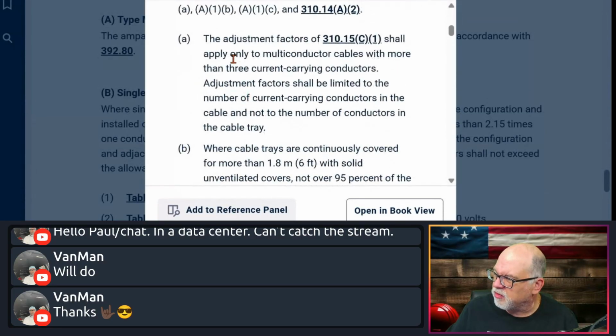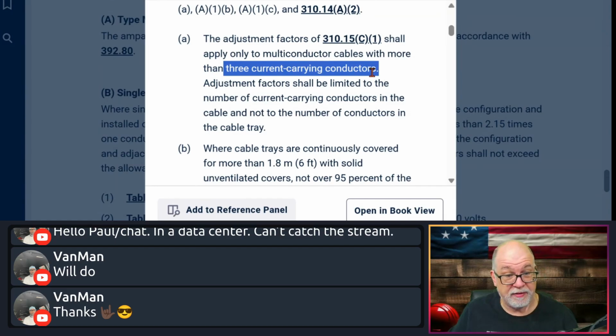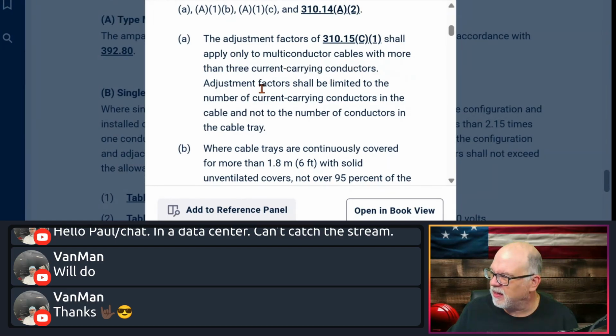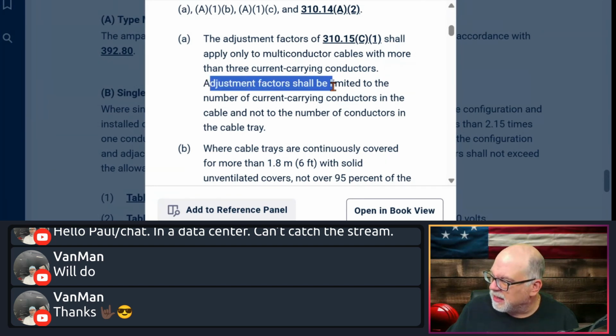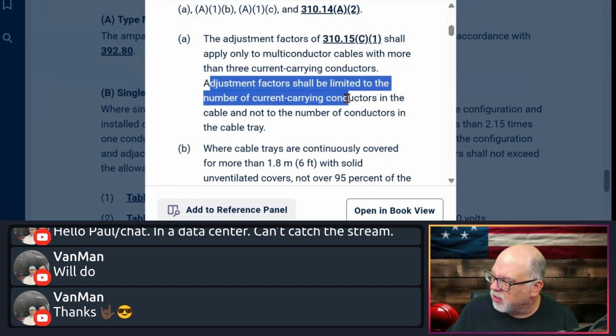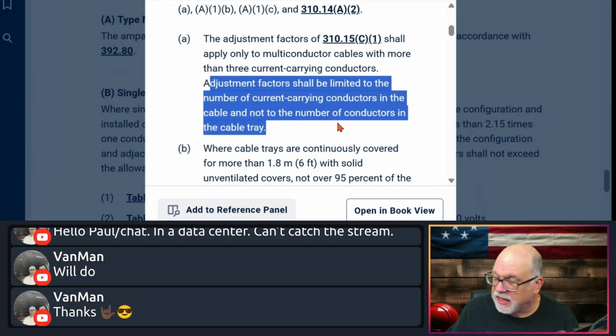It mirrors things about adjustments. So the adjustment factors in 310.15(C)(1) that I was talking about shall only apply to multi-conductor cables with more than 3 current carrying conductors. Important. If it's more than 3. So if it's 3, it's okay. It says more than 3. It says adjustment factors shall be limited to the number of current carrying conductors in the cable, not the number of conductors in the cable tray.